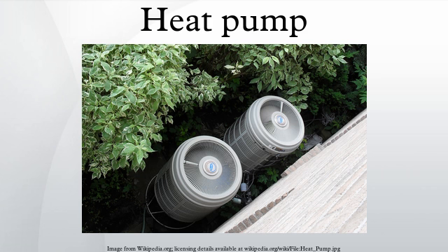Heat pumps are used to provide heating because less high-grade energy is required for their operation than appears in the released heat. Most of the energy for heating comes from the external environment, and only a fraction comes from electricity. In electrically powered heat pumps, the heat transferred can be 3 or 4 times larger than the electrical power consumed, giving the system a coefficient of performance of 3 or 4, as opposed to a COP of 1 of a conventional electrical resistance heater, in which all heat is produced from input electrical energy.